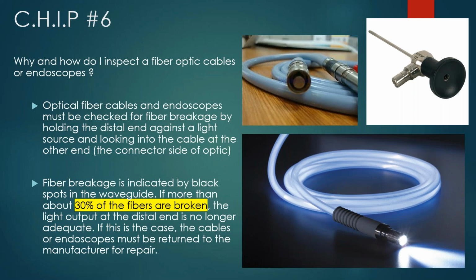Tip number 6, why and how do I inspect fiber optic cables or endoscopes? It's another very important thing that is oftentimes missed. We think and we hope that these just work, but optical cables and endoscopes must be checked for fiber breakage by holding the distal end against the light source and looking into the cable at the other end.